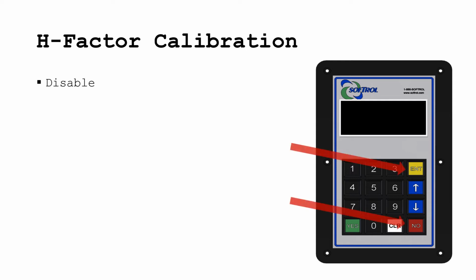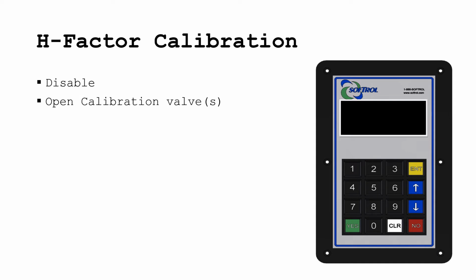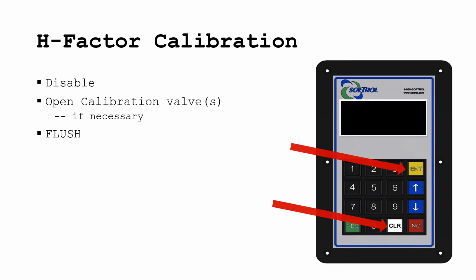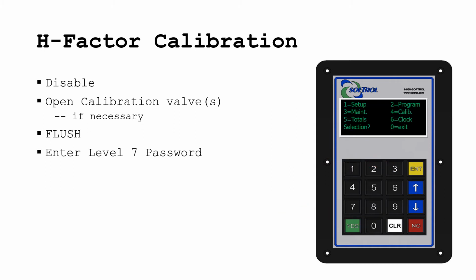First you disable the system. Then, you open the calibration port valve or valves if necessary. Next, you flush the system. After, you enter in the level 7 password to bring up the main menu. From there, you press the 4 key for 4 equals calib.